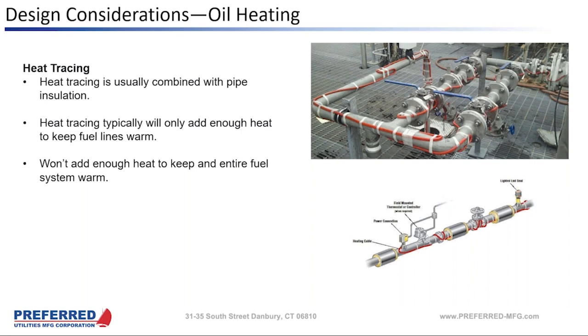And this is a good solution for keeping the most vulnerable part of your fuel system warm, the exposed overhead piping. But it's really just part of this complete breakfast. It'll keep your exposed piping warm. It won't add enough heat to a system to keep all of your fuel warm. But heat tracing is very common and does a good job with the most vulnerable part of your fuel system piping.